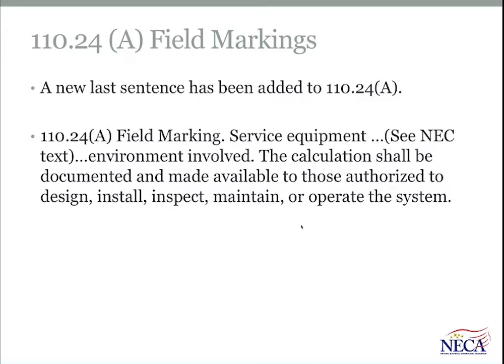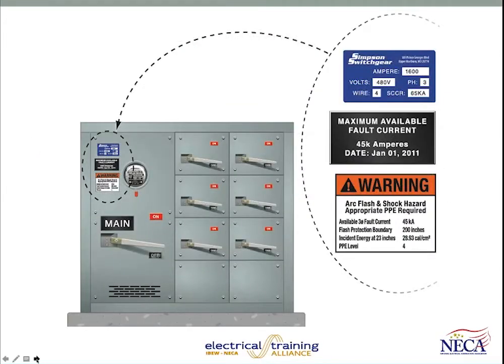That new sentence is, the calculation shall be documented and made available to those authorized to design, install, inspect, maintain, and so forth that system. So the AHJ certainly has a little bit more leverage, if you will, in getting information to ensure that the equipment being installed or worked on maintains its rating as required by 110.24. And the graphic that we use shows 3 labels. You've got a manufacturer's label on the top. You've got the 110.24 label, the black label in the middle there, where it shows maximum available fault current at 45,000 amps and the date the label was installed. The arc flash warning label below is the label that would be required by 110.16.